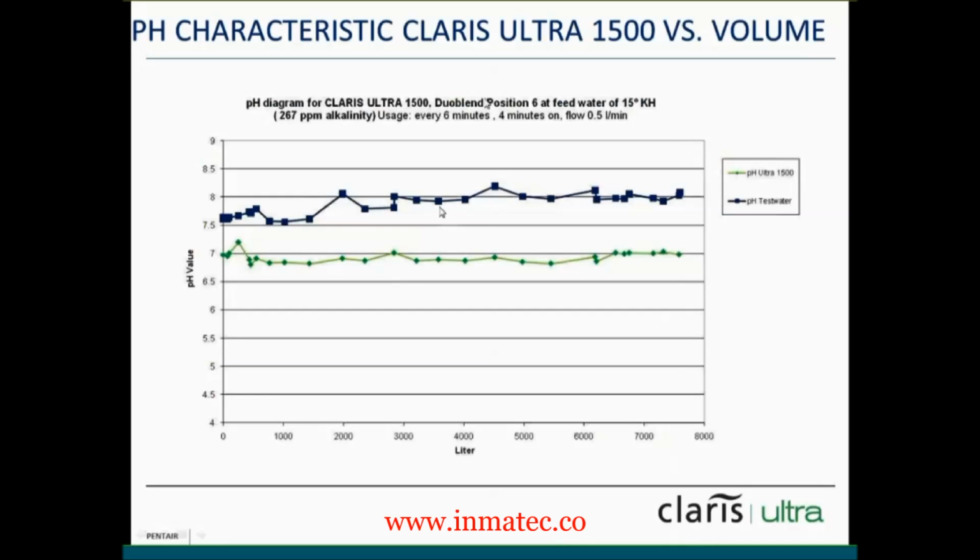pH characteristics of Claris Ultra 1500 versus volume. As you notice, here's the test water coming in. The test water varied more greatly than the water coming out. This shows the pH stabilization and control that's capable with Claris Ultra when it's selected properly.